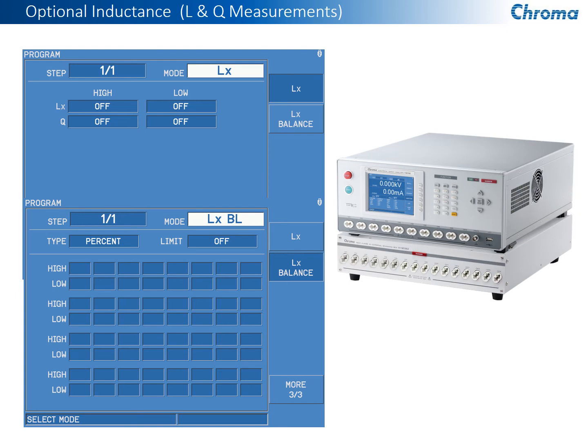Another test that we do that is an option is we can also include an LCR meter, one of our LCR meters with the actual 19036. We have connections on the back of the 19036 that bring the measurement capability from the LCR meter all the way out to each individual channel on the connections here that you see on our 19036 safety tester. So when we do that, we can now measure the actual inductance of each winding, but we can also do, in addition to each winding, a comparison to measure the balance. Again, balance critical to stators and electric motors.